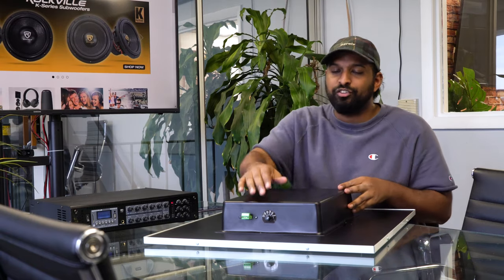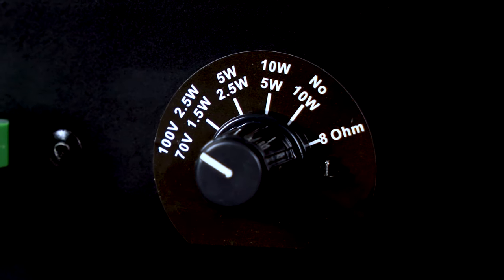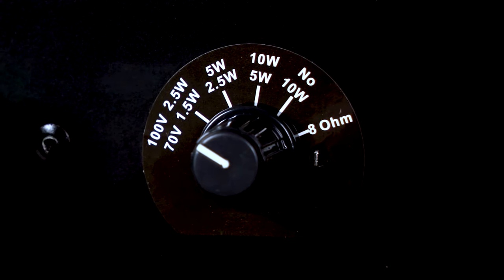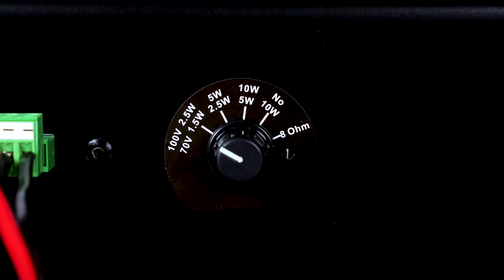Before we say anything else, let's go check out a demo we have set up. All right guys, we are all set up with the demo here. I have a DCS8T in the ceiling and also have one here in front of me. Now, since this is a 70-volt speaker, I just want to show you the 70-volt tap over here. So a 70-volt tap is basically a built-in transformer in the speaker that pulls a fixed amount of wattage from the amplifier to the speaker. In less technical terms, that means I have options in how many watts are going from the amplifier to the speaker.